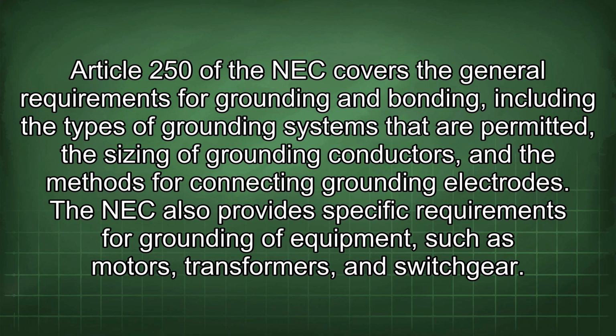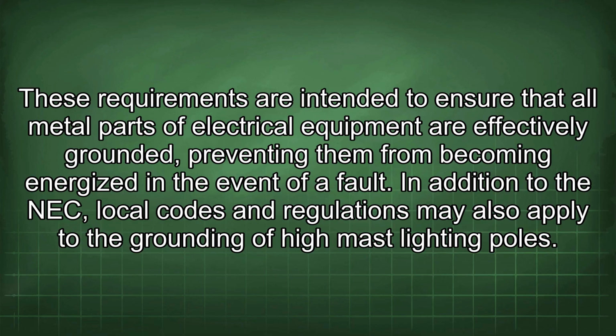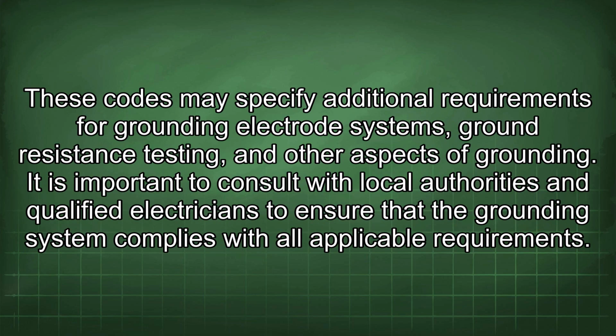The NEC also provides specific requirements for grounding of equipment, such as motors, transformers, and switchgear. These requirements are intended to ensure that all metal parts of electrical equipment are effectively grounded, preventing them from becoming energized in the event of a fault. In addition to the NEC, local codes and regulations may also apply to the grounding of high-mast lighting poles. These codes may specify additional requirements for grounding electrode systems, ground resistance testing, and other aspects of grounding. It is important to consult with local authorities and qualified electricians to ensure that the grounding system complies with all applicable requirements.